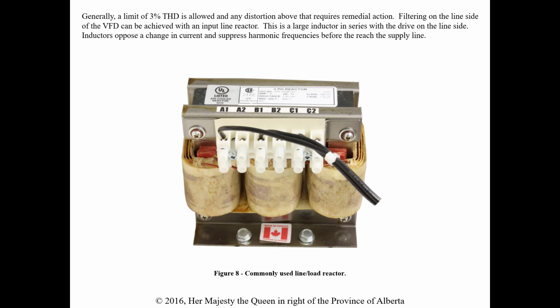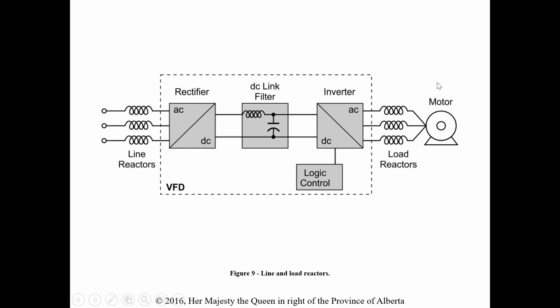Okay, so if it's determined that it is higher than that, we would put filtering on the line side. That's to protect the utility, and again, we would also potentially have it on the load side to protect the motor. So what is a line reactor? It's a large inductor in series with the drive on the line side. Inductors oppose a change in current and suppress the harmonic frequencies before they reach the supply line. So we can do this on the load side as well. So here are our line reactors, again protecting our utility, and our load reactors protecting our motor.